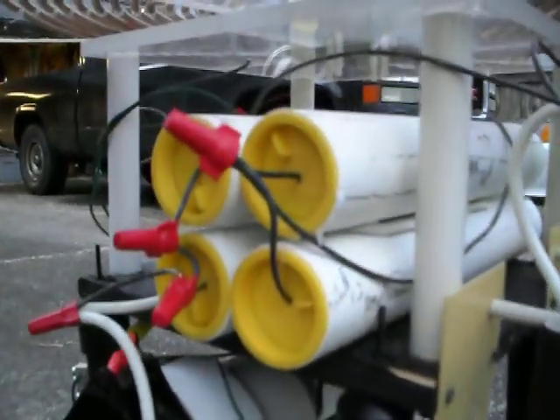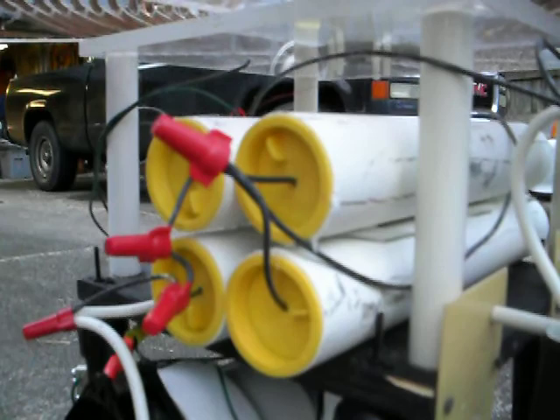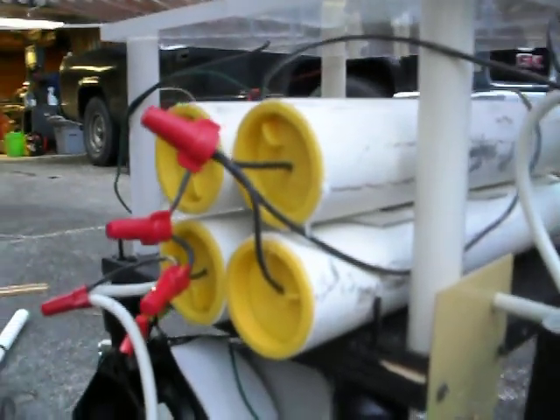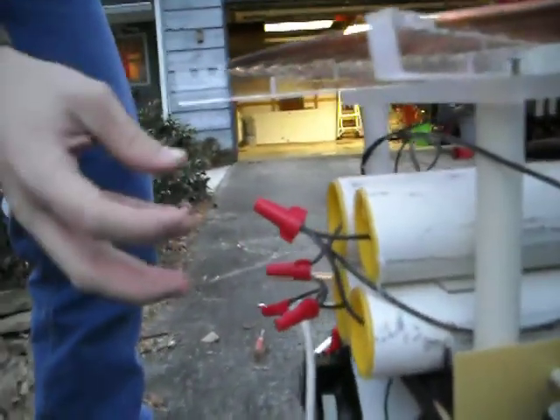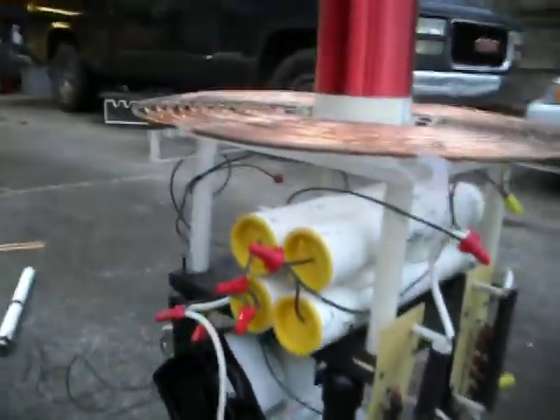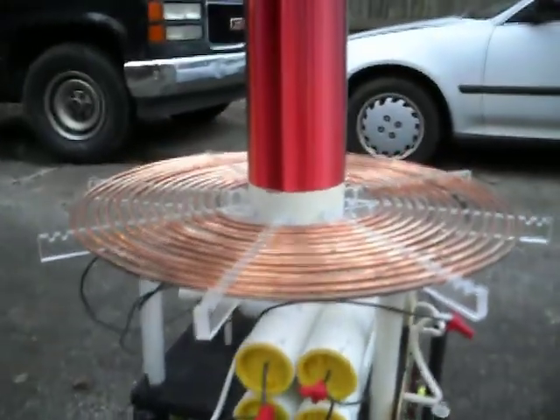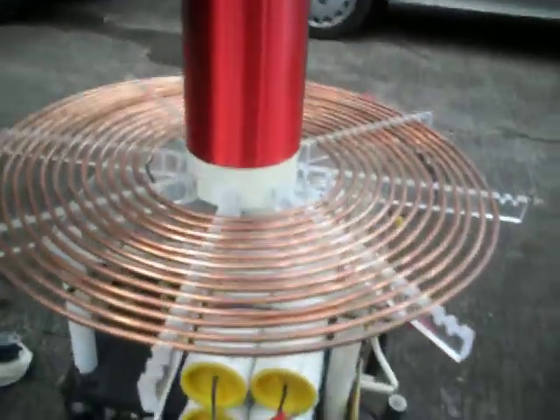Inside each one of these tubes is 10 capacitors. Now what they do is they function as an MMC, multiple mini capacitor array. So it gives those 40 capacitors total the function of being one large capacitor. This capacitor bank itself is rated at 18 nanofarads and 40 kilovolts voltage rating. From that, it runs to the spark gaps.